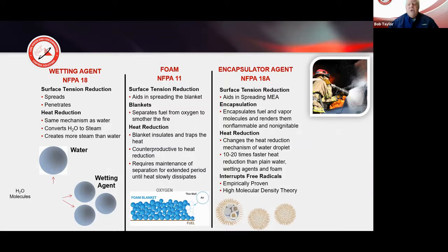So when we look at different items, we look at wetting agents. Wetting agents fall under the guidance of NFPA 18. They are predominantly used because they reduce surface tension, allowing them to spread and penetrate, which is often why they're used in wildfires. They do have heat reduction—same mechanics as water, converting H2O to steam—a bit more efficiently, but not as efficiently as what F500 encapsulating agent does with capturing heat and rapid reduction.